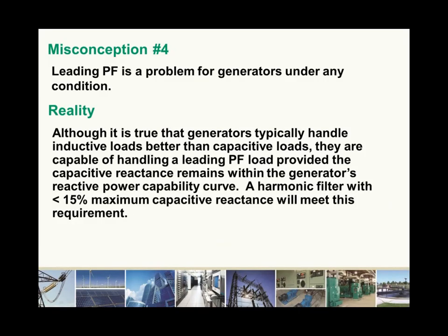So misconception number 4 is that leading power factor is a problem for generators under any condition. Although it is true that generators typically handle inductive loads better than capacitive loads, they are capable of handling a leading power factor load provided the capacitive reactance remains within the generator's reactive power capability curve. A harmonic filter with less than 15% maximum capacitive reactance will meet this requirement. Therefore, if you have a filter of this design, you do not require switching out of the capacitors under light loads. But if it's above the 15%, or typically in the 30 to 40% range, you will require those contactors.